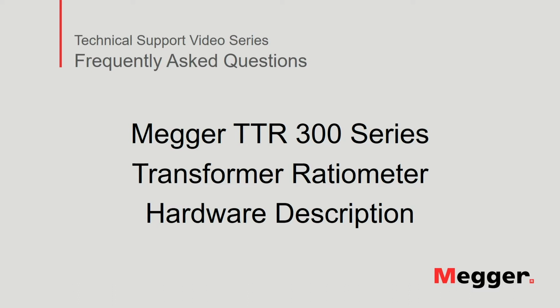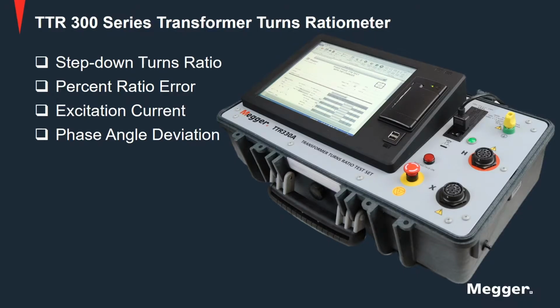In this video, we will review hardware features of the Megger TTR300 Series transformer ratio meter. Let's get started. The TTR300 series utilizes the step-down measurement principle by applying voltage to the high voltage winding and accurately measures resulting voltage from the low voltage winding of the transformer.